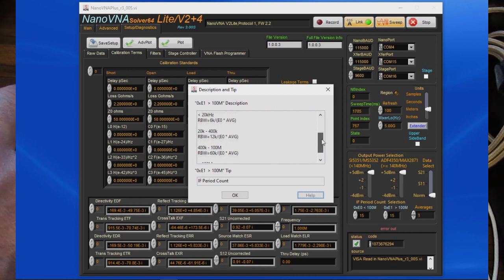Anyway, so for below 20 kilohertz, for example, we take 6 kilohertz and we divide that by E0 multiplied by the average. So it's going to take whatever is in this E0 register, multiply that by the number of averages that you have here, divide that into 6,000, and that gives you your IF bandwidth.